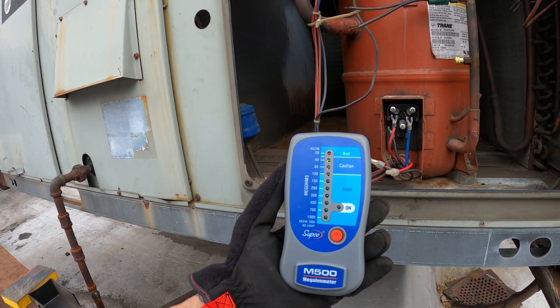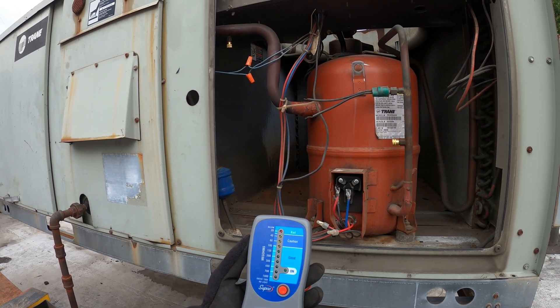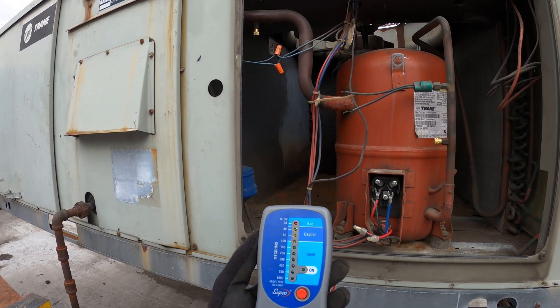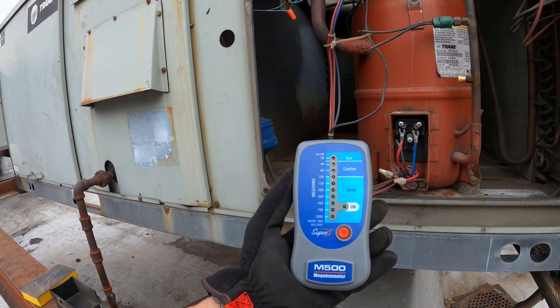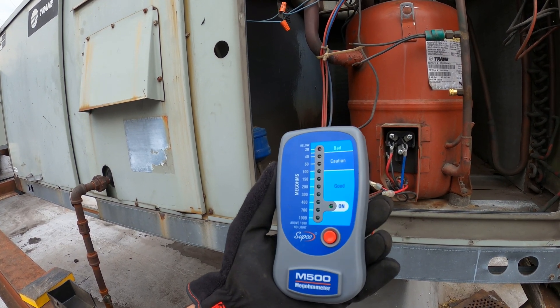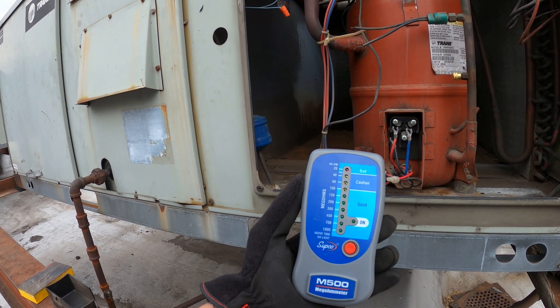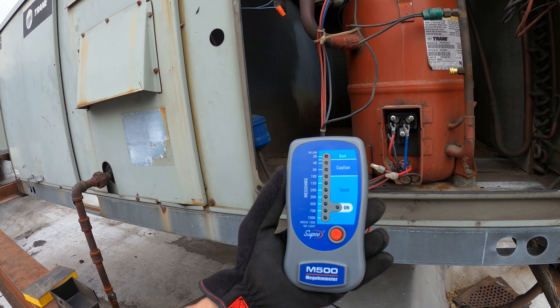This video was made for professionals only. You should have an EPA license before touching any type of equipment that has refrigerant. And before using this megohmmeter, I highly recommend you read the manual and understand how a megohmmeter works, because running this test you are applying 500 volts to these windings on this compressor. Safety first, everyone.